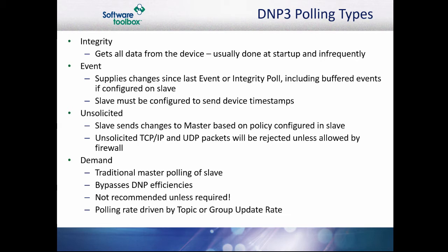Demand polling allows the driver to work in a traditional master-slave polling method. This will retrieve data for points defined for demand polling whether the data has changed or not. Be aware that this removes the efficiencies of the DNP3 protocol and is not recommended unless necessary.